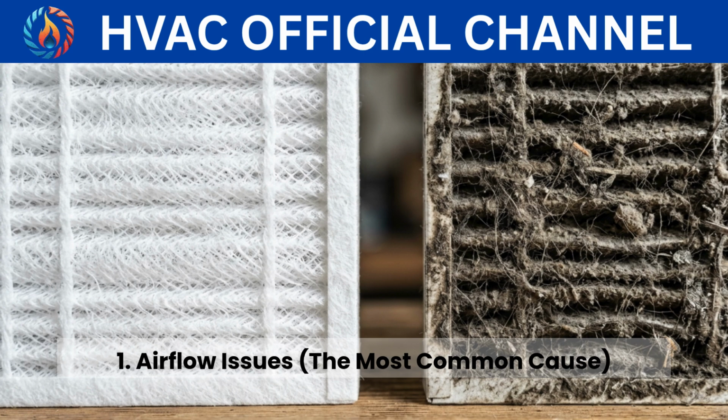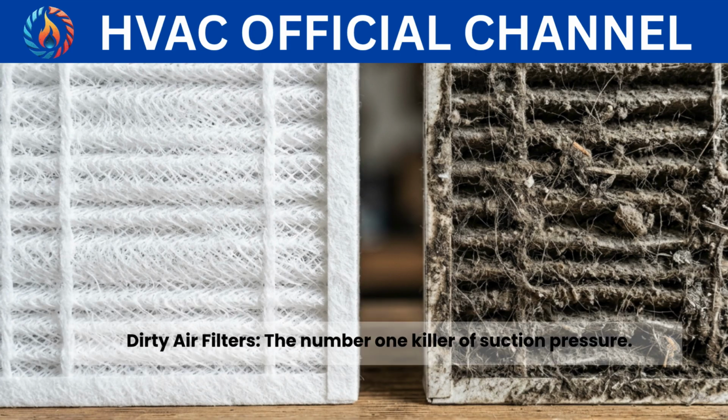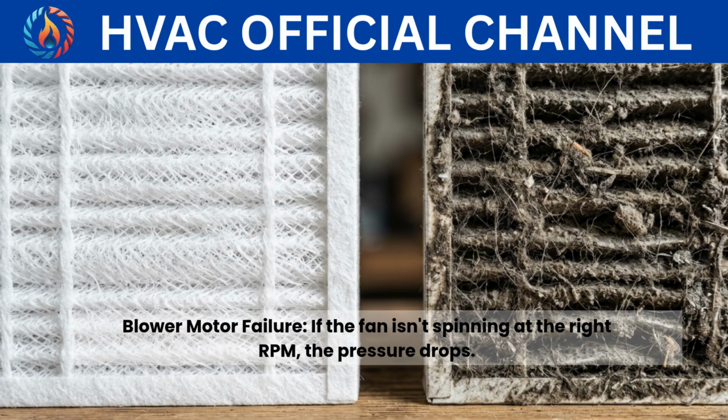The big four causes. 1. Airflow issues, the most common cause. If the air cannot pass over the evaporator coils, the refrigerant cannot pick up heat. If there is no heat to pick up, the refrigerant remains a cold liquid-gas mix, and the pressure stays low. Dirty air filters, the number one killer of suction pressure. Dirty evaporator coils. Dust acts as insulation. Blower motor failure. If the fan isn't spinning at the right RPM, the pressure drops.